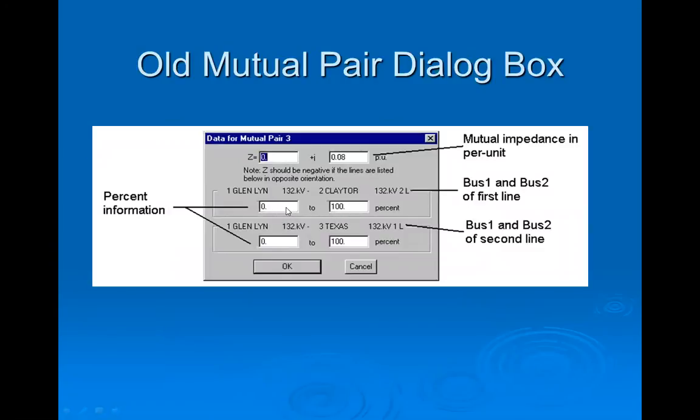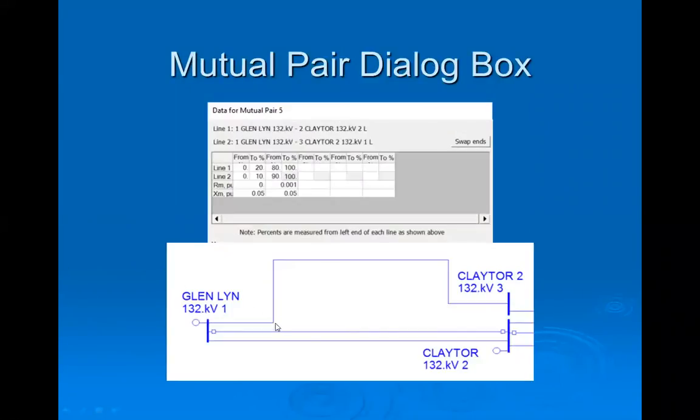have only one number. So for this example, it will be impossible to represent it. And what you will have to do in this case, if you use the old version, is to put a tap bus here and another tap bus here and a tap bus here and another tap bus. So you need to put like 4 tap buses there to correctly represent this, or maybe if you need to do that on this line too, there are a lot more tap buses that clutter and make your model very difficult to read.